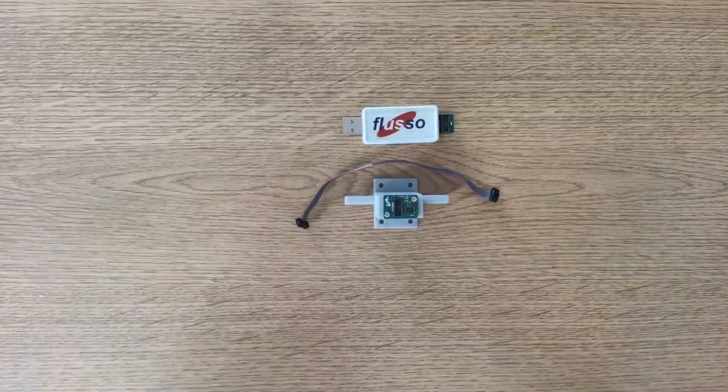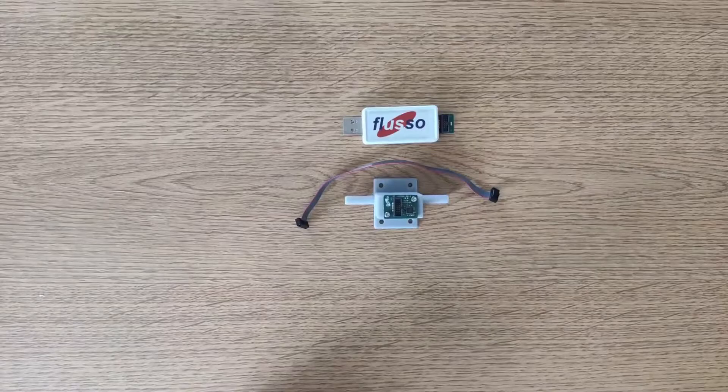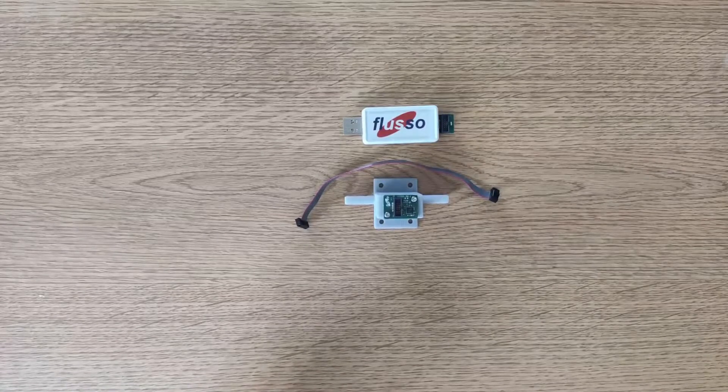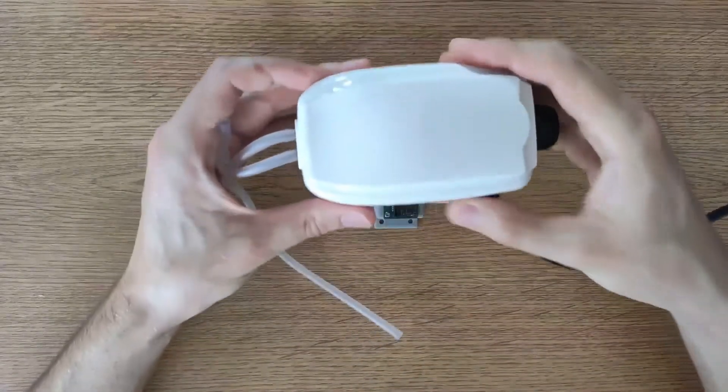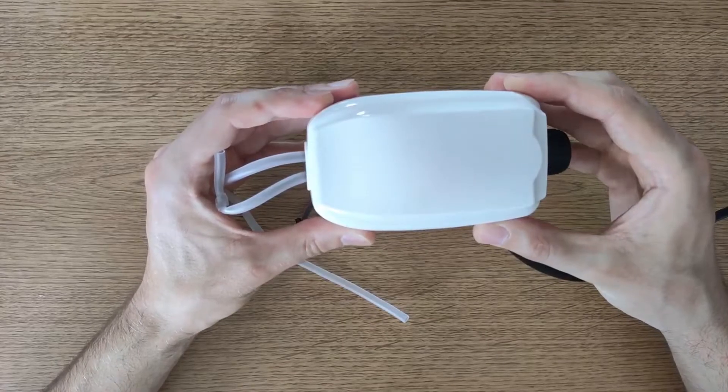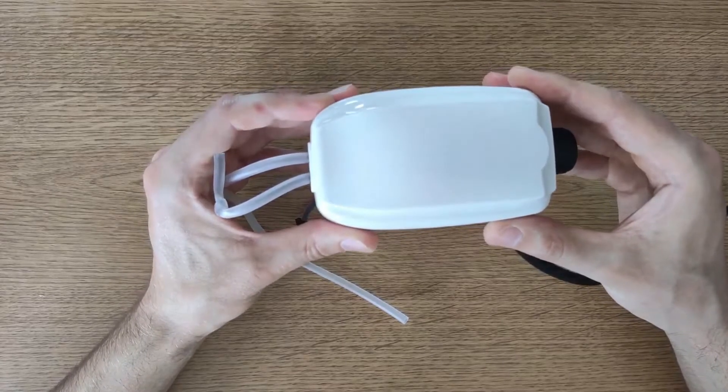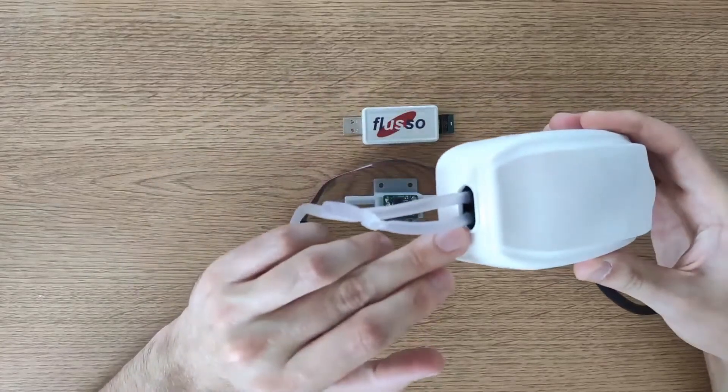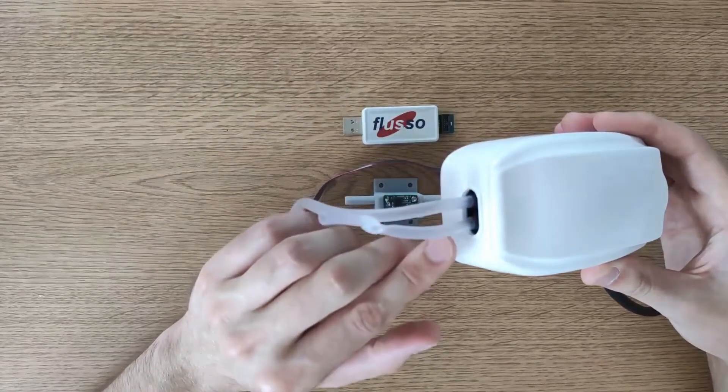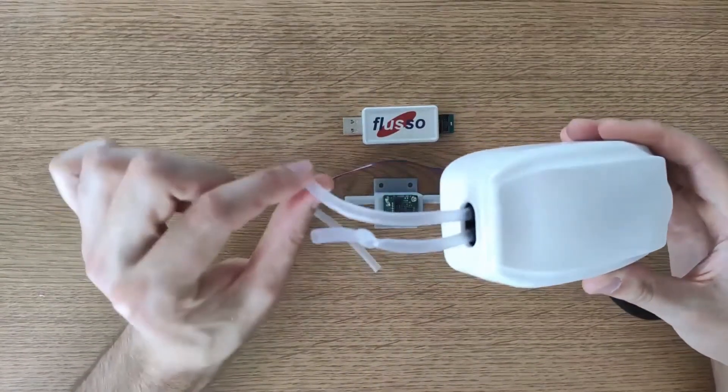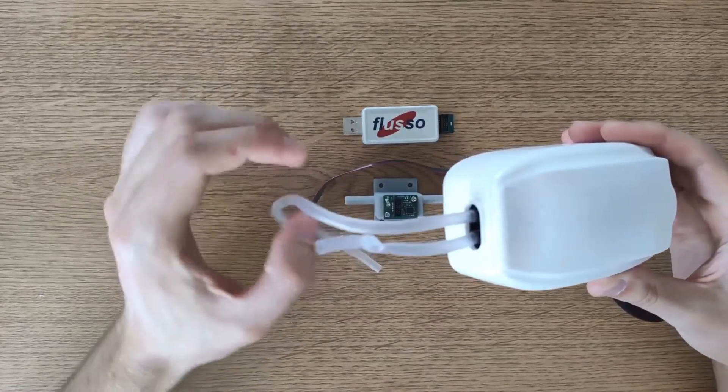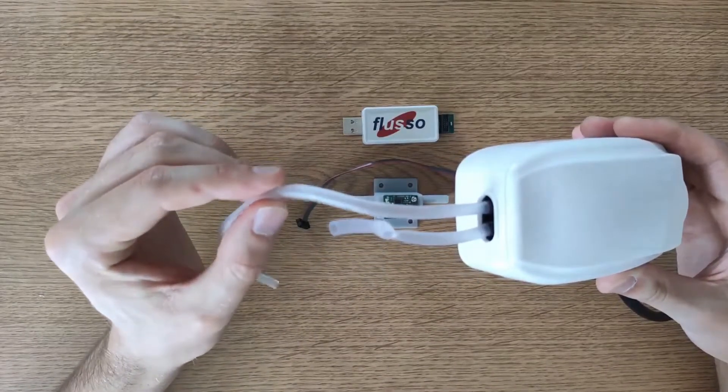In order to evaluate the sensor you'll need to pass air through it. You could use a lab air source or you could use something as cheap and simple as this. This is a fish tank pump that I bought for just a few dollars. It has two outlets and I've just taken one of the outlets and blocked it off. I'm going to use this second outlet to pass air through the FLS110.